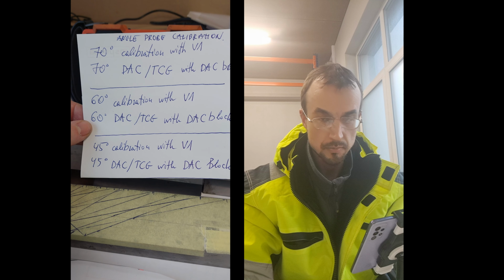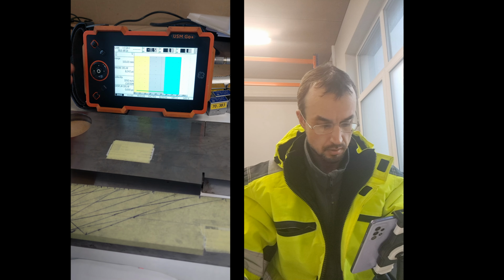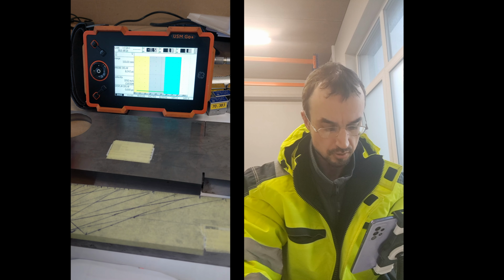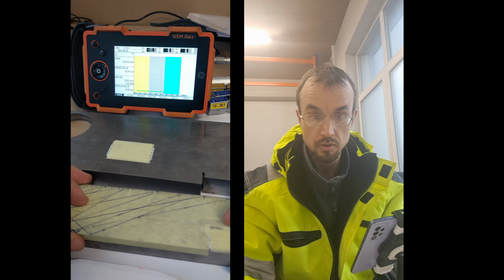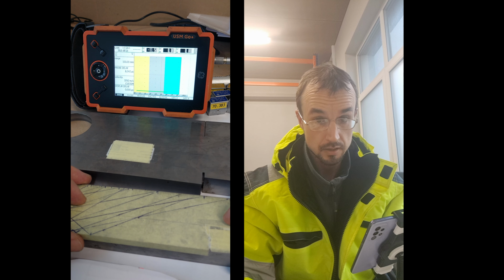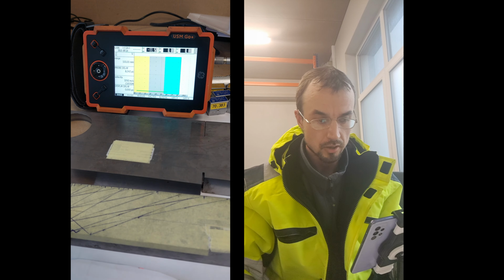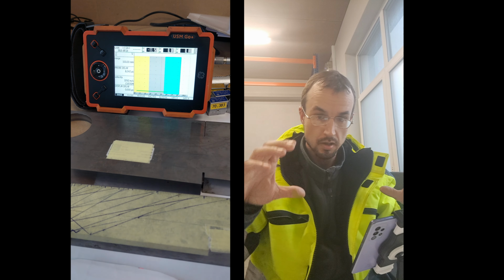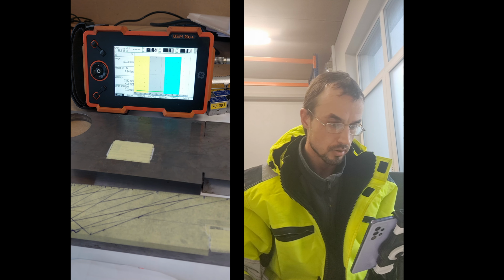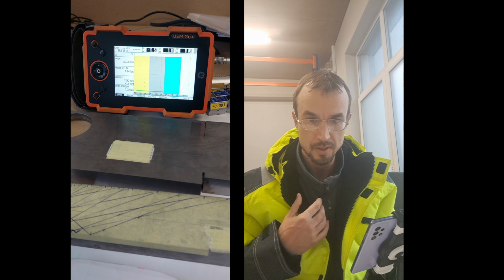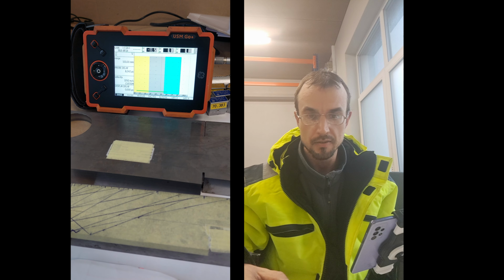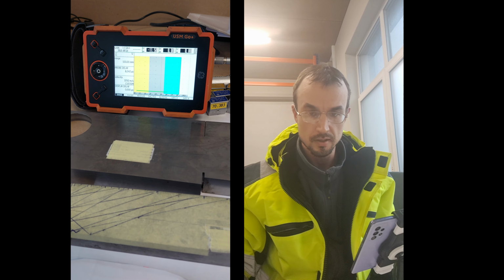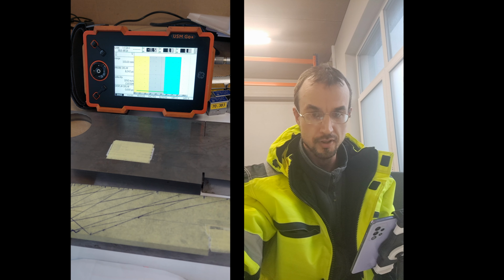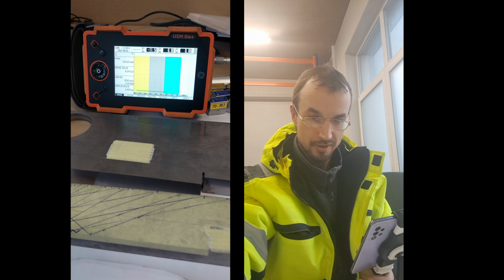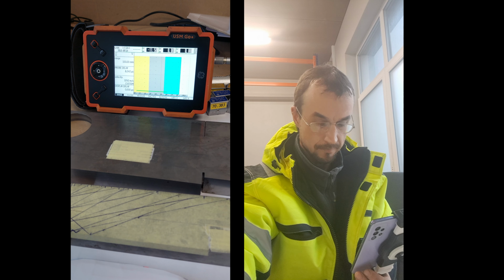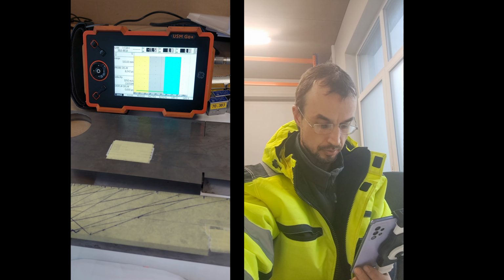So that's the plan. What we need to have is the machine, probes, cables, V1 block, and DAC block, and then that's it for the calibration. Then I'll try to put it into one screen so you can see better, and I myself can see better later when I look at my videos several months later, when I forget how to work with it. Okay, so I'm pausing this and starting the calibration of the 70-degree probe.